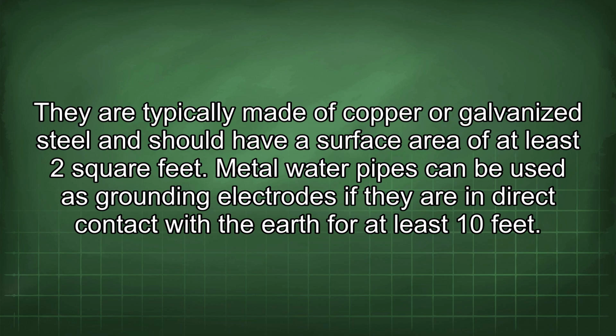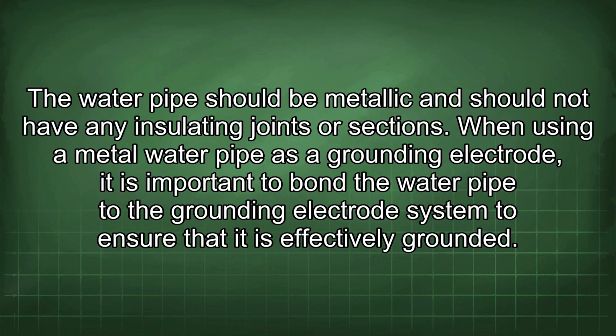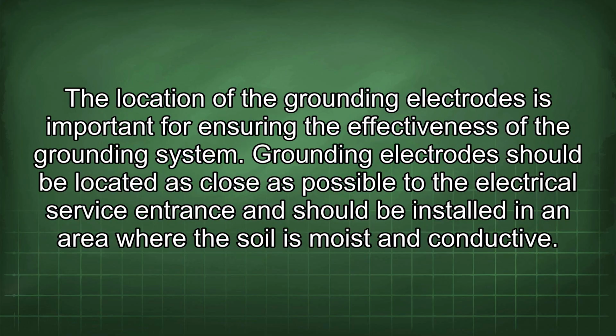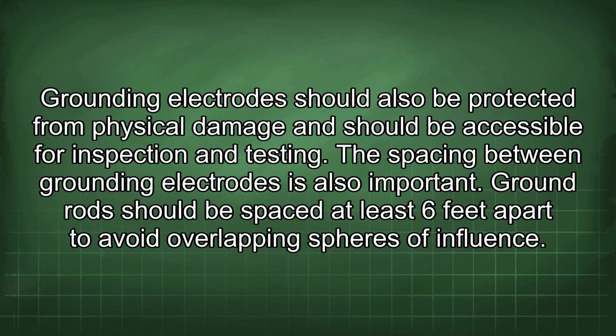Metal water pipes can be used as grounding electrodes if they are in direct contact with the earth for at least 10 feet. The water pipe should be metallic and should not have any insulating joints or sections. When using a metal water pipe as a grounding electrode, it is important to bond the water pipe to the grounding electrode system to ensure that it is effectively grounded. The location of the grounding electrodes is important for ensuring the effectiveness of the grounding system. Grounding electrodes should be located as close as possible to the electrical service entrance and should be installed in an area where the soil is moist and conductive. Grounding electrodes should also be protected from physical damage and should be accessible for inspection and testing.